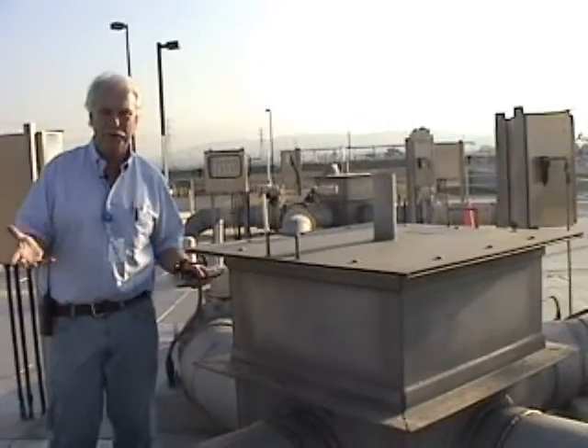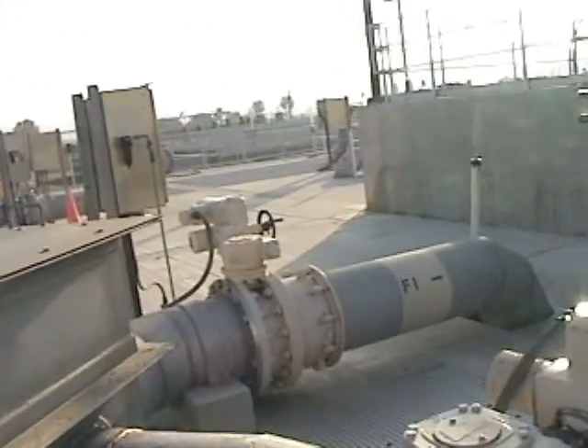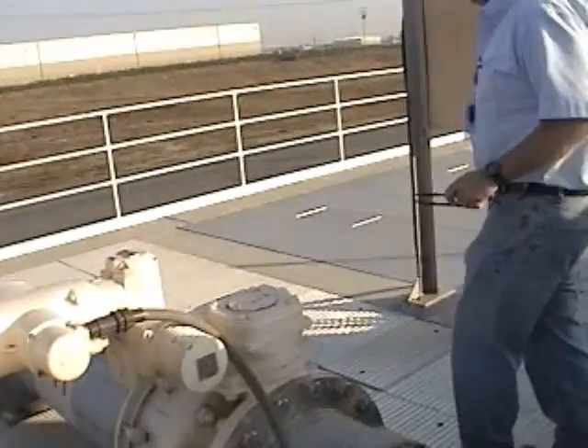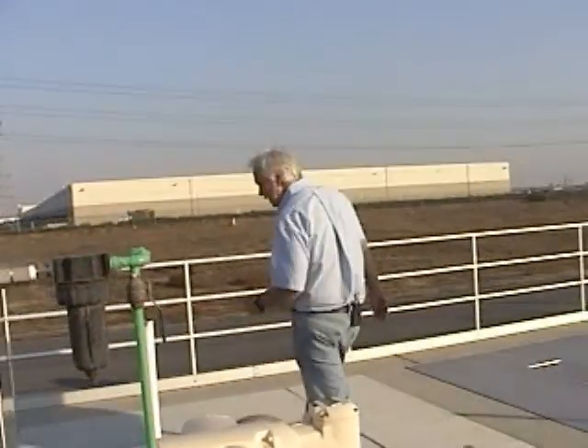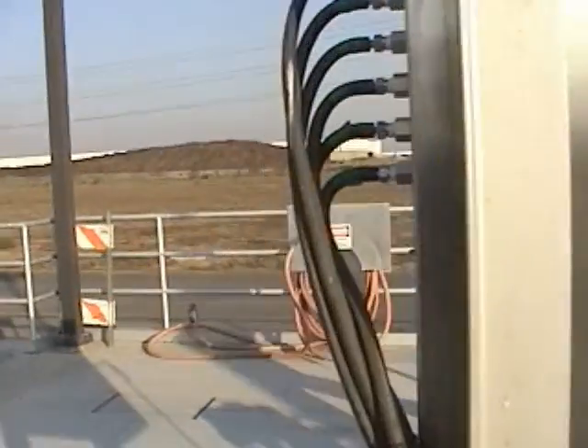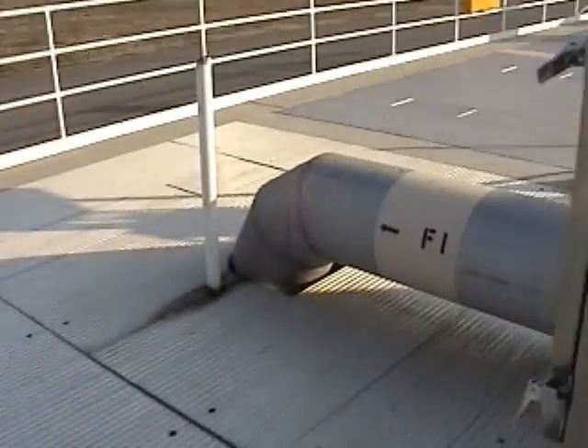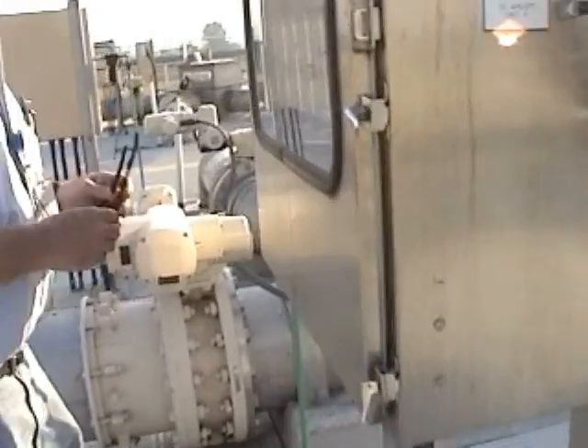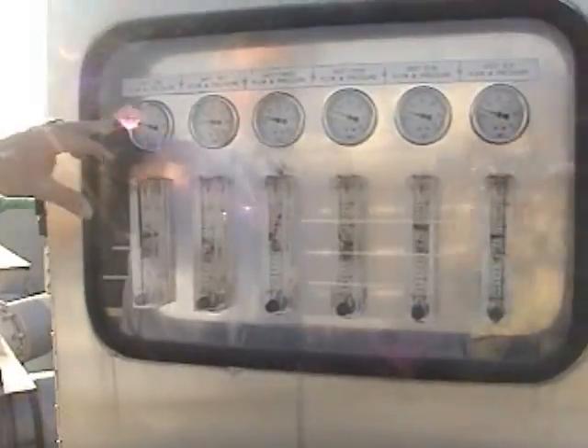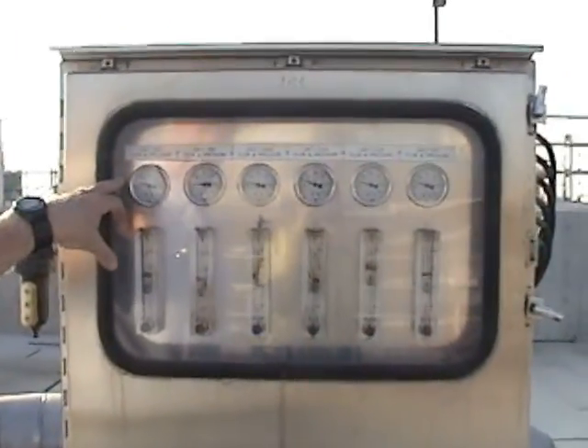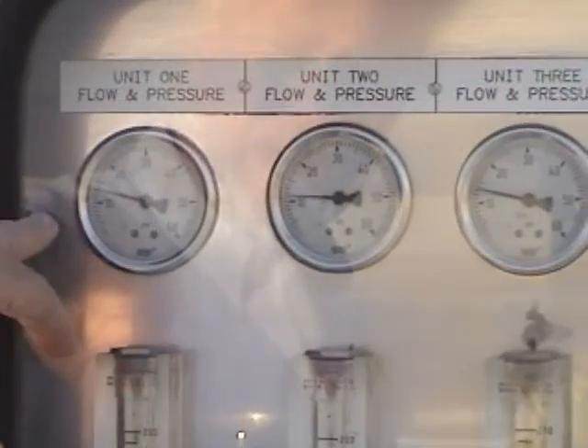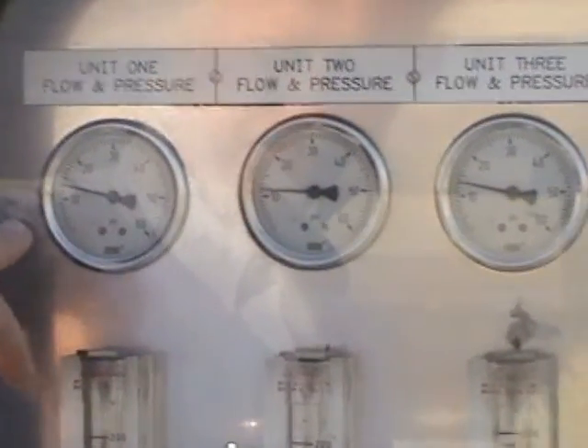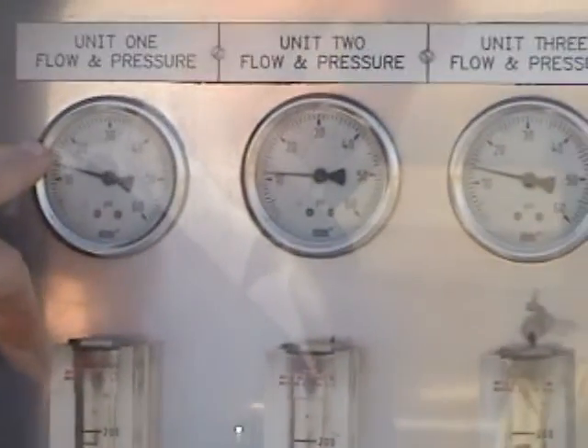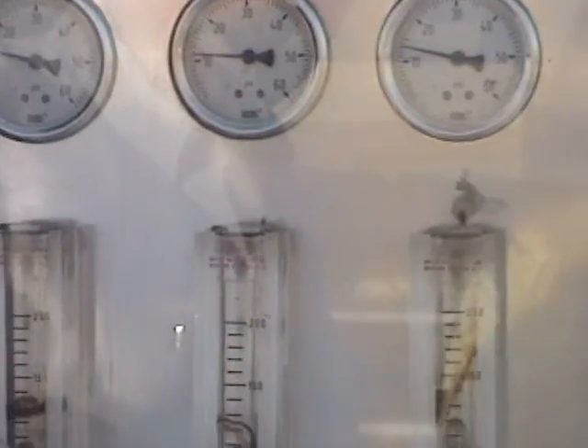I've talked to a lot of people about these filters, and each person will call it something different, but generally everyone agrees on the term module. Things you want to look for is on this air pressure gauge right here. You're looking at about 10 psi on pressure, and the flow at 100. See that?